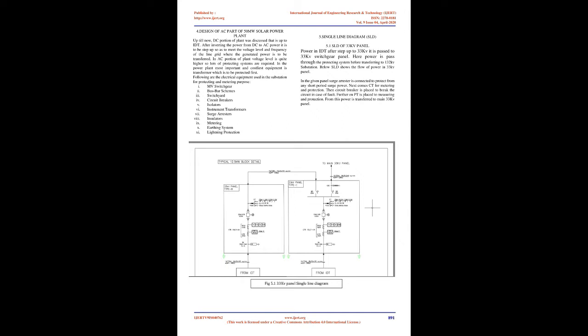3.1 Study of one block of 6.25 MW. Each block consists of a total of 858 tables and 39 inverters. So, per inverter, 22 tables are connected. The grouping of tables is done, with 22 tables in one group connected to one inverter. A total of 8 such blocks are made for the 50 MW plant. Per block, 6.25 MW. Inverter, 160 kW, 45% overloading.